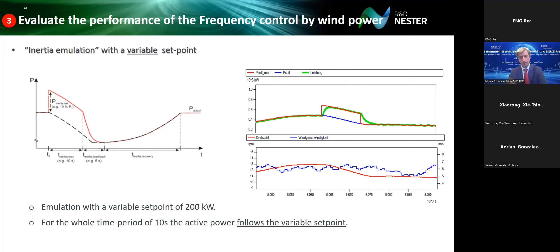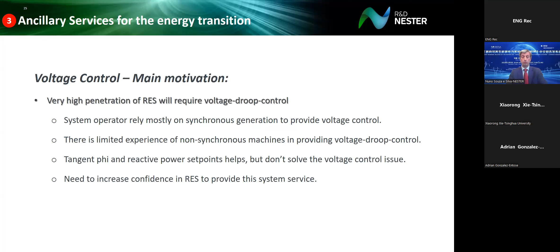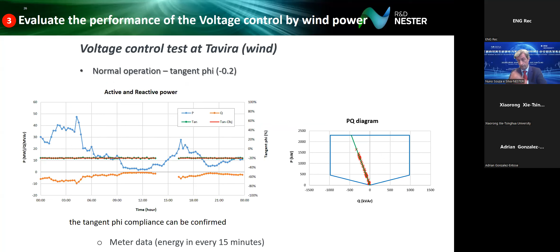Then another aspect is voltage control. We looked into voltage droop control, in particular with wind, making sure that the tangent phi was below 20%, so minus 0.2, and we managed to see that compliance with this tangent phi requirement was confirmed, also clearly observed in the PQ diagram, with the data points showing the operating mode inside the operating boundaries.